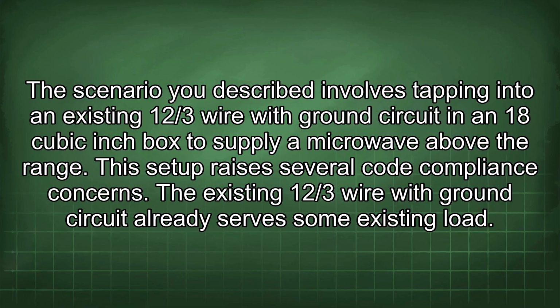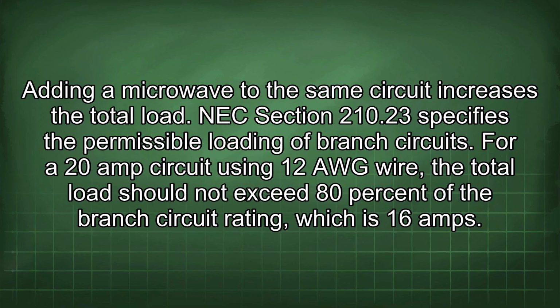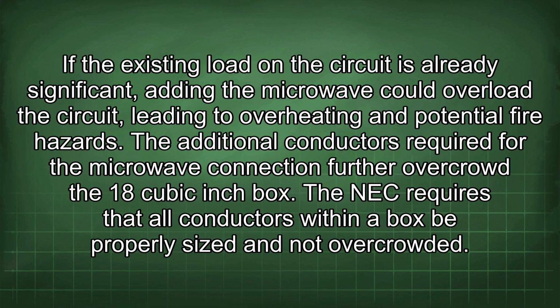The existing 12/3 wire with ground circuit already serves some existing load. Adding a microwave to the same circuit increases the total load. NEC section 210.23 specifies the permissible loading of branch circuits. For a 20 amp circuit using 12 AWG wire, the total load should not exceed 80% of the branch circuit rating, which is 16 amps. If the existing load in the circuit is already significant, adding the microwave could overload the circuit, leading to overheating and potential fire hazards. The additional conductors required for the microwave connection further overcrowd the 18 cubic inch box.